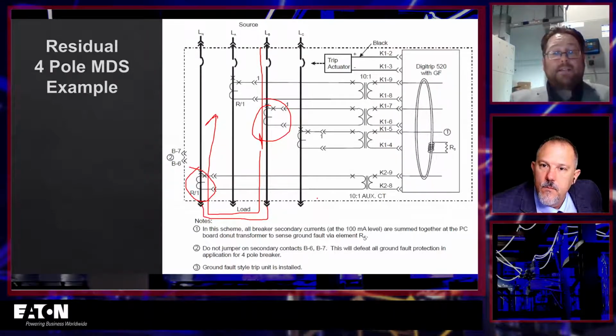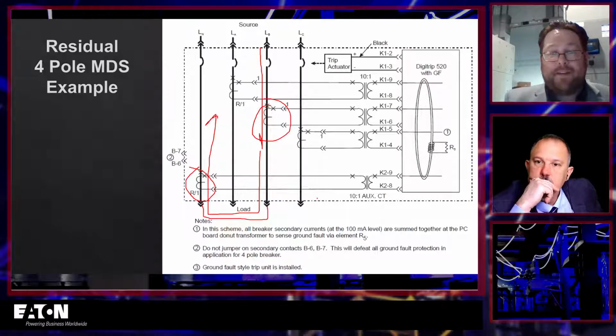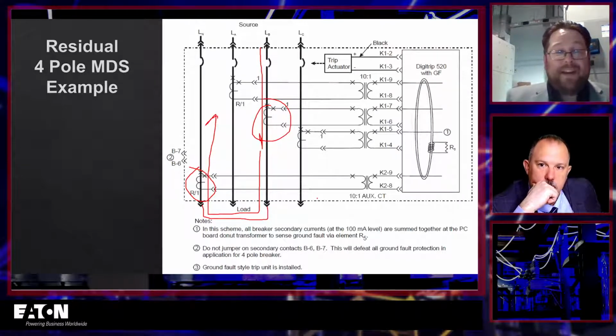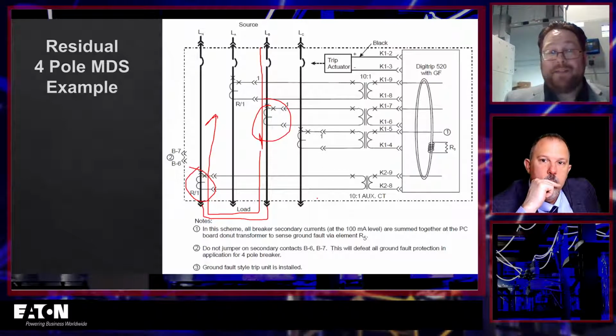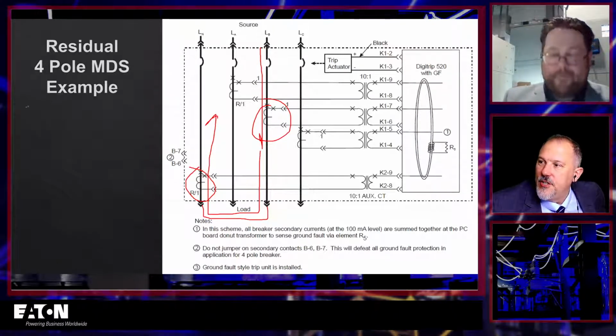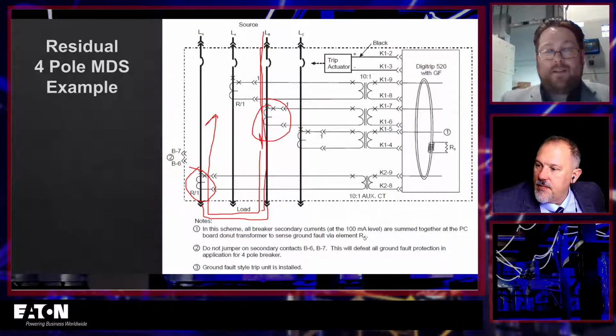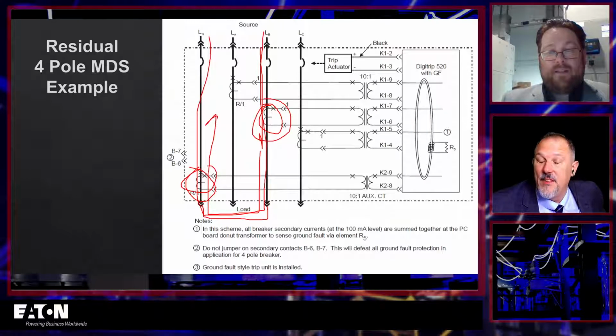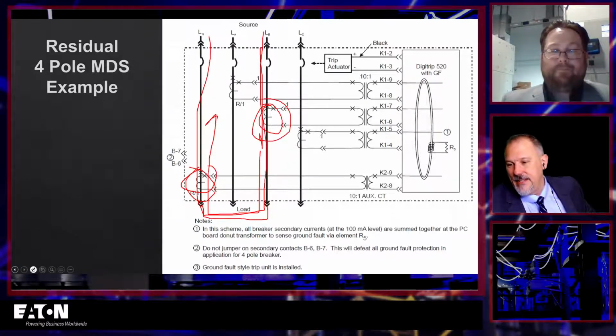Yeah, because if you think about your phase protection, CT polarity doesn't actually matter on overcurrent. That's right. But in this instance, we're confirming we have no ground current by using all of our CTs, so we need to confirm all of them are wired to the proper polarity. That's right. And that's how you do that: you're physically injecting current down through this one and then back up through that one. And now you know that it should not trip because this current and this current will be the same if they're both the right polarity. I love it. Okay, I get it now.